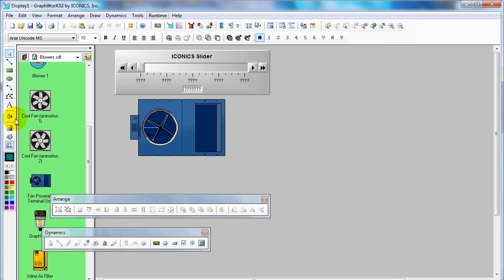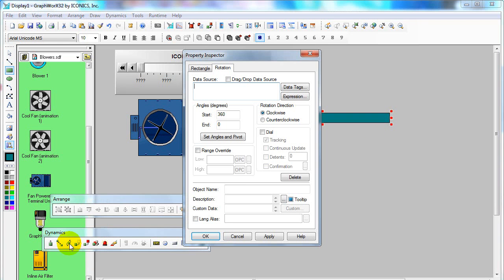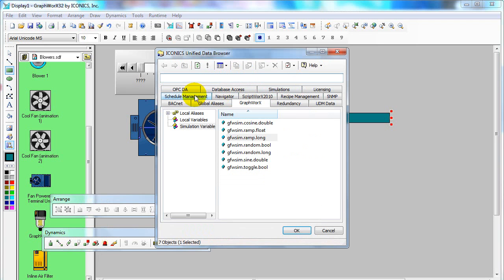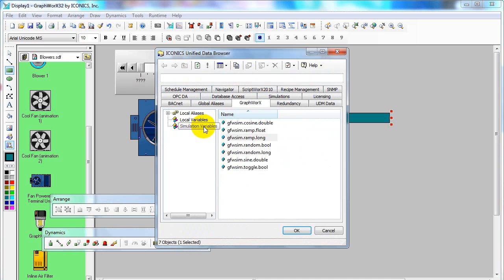Now get back to Configure. We can apply the rotation dynamic to the object. In this example, I'll use a simple object — the rectangle — and apply the rotation dynamic to it. You can select data tags and choose the OPC DA signal, which is the OPC tag from the OPC server, or you can use the simulation variable.